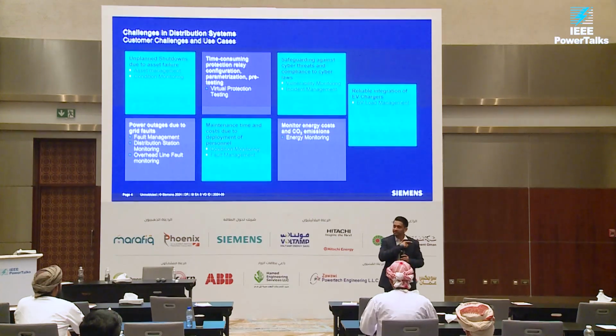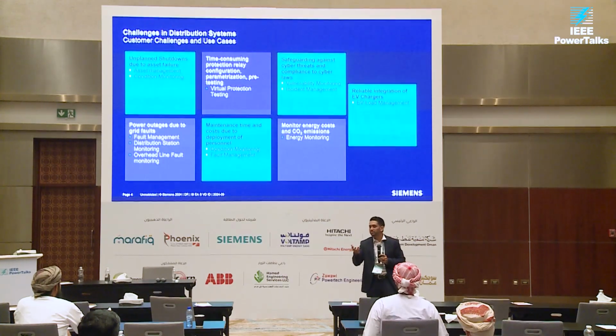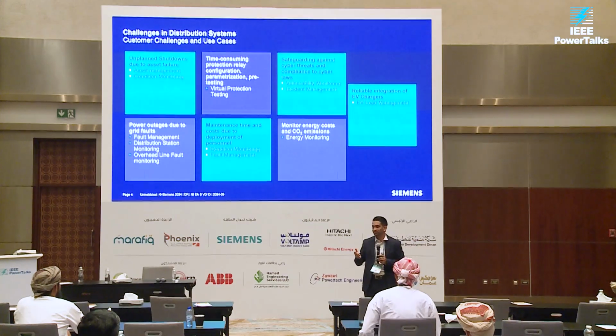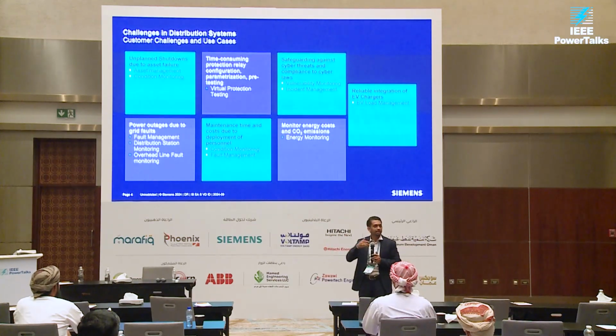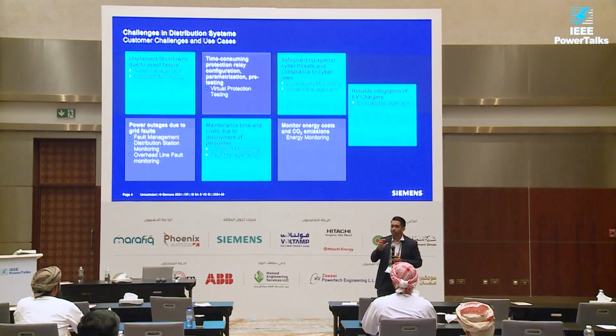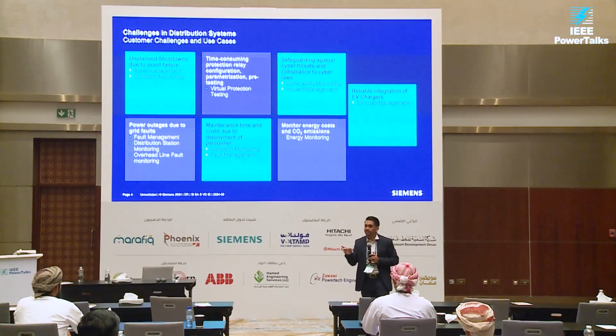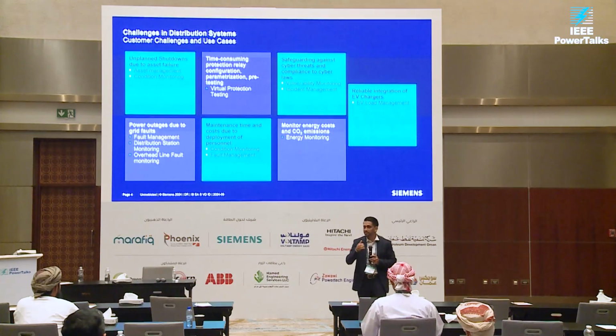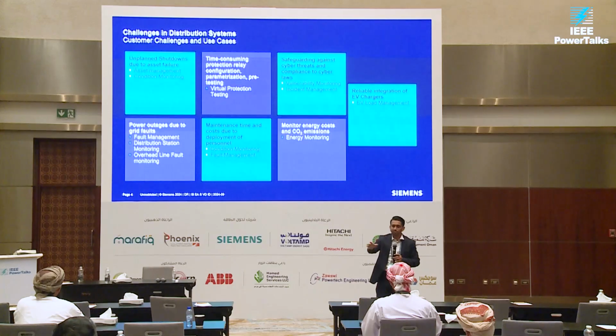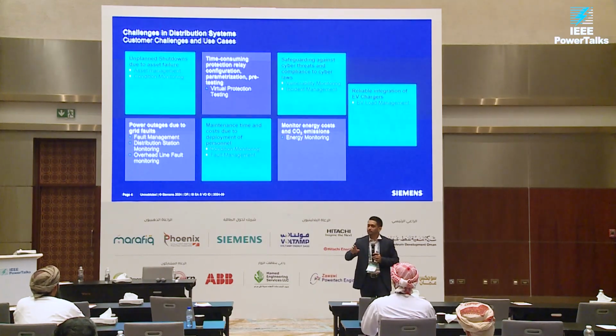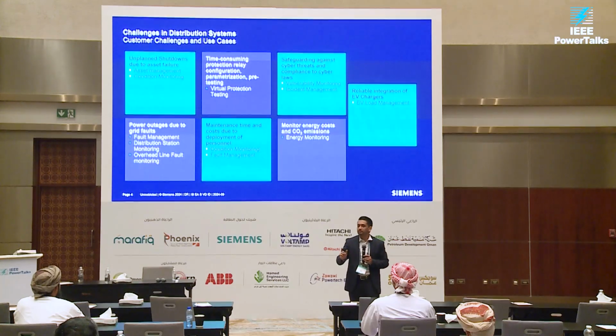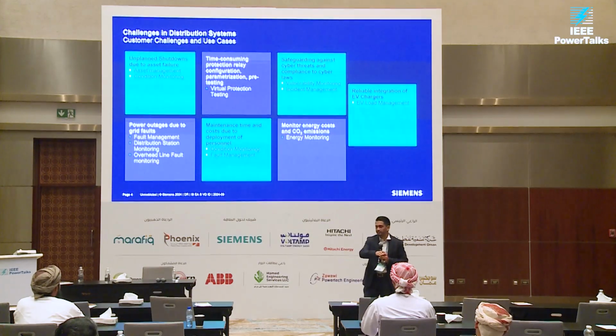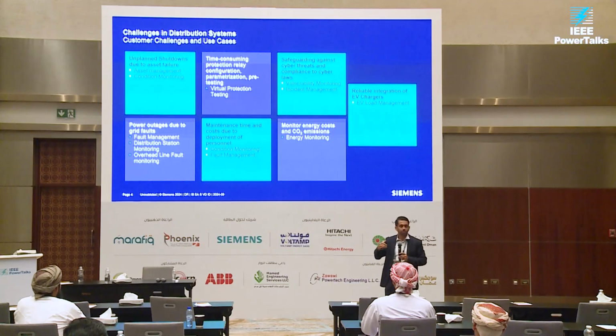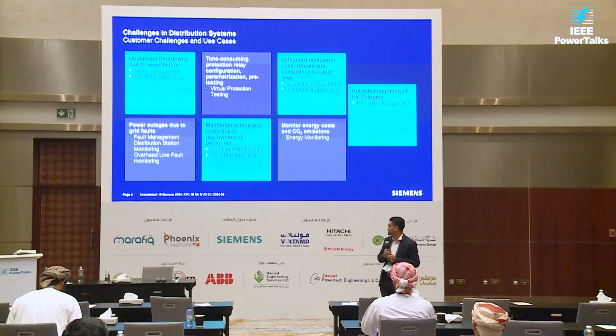When you connect chargers to the grid, the grid has issues managing it, since the plug-in and plug-out of cars isn't constant. Cars may charge in 45 minutes, but trucks don't charge that fast - they take 6 hours because their batteries are bigger. So you need a load management system that can distribute power within the limit set by distribution operators like NEDC. If NEDC says a station's maximum capacity is 900 kilowatts, even if 10 cars plug in, we never cross that limit. This is a challenge we need to take care of as more EV infrastructure is developed.